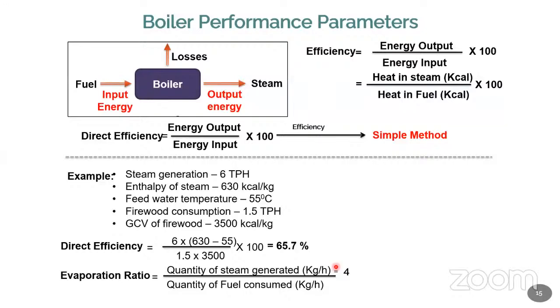For example, it may be around 1000 kg or 1000 liters. Of course, kg and liter are the same for water because the specific gravity of water is 1. Therefore, the volumetric value and mass flow value are the same for water. That's why water is taken as a benchmarking value. So 1000 kg or 1000 liters of water per hour is taken, and 250 kg of fuel is taken. So 1000 divided by 250 equals 4. It's very simple. So measurement of water and measurement of fuel will give the evaporation ratio.